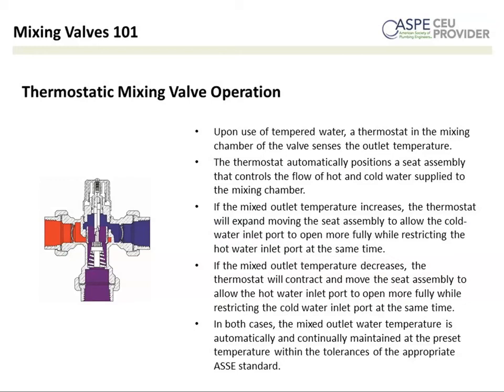And the heart of any thermostatic mixing valve, again, we talked about this earlier, is that thermostat. In this case, it's in the center of that diagram, and it's a paraffin-based element, which has some wax mix, some copper, a diaphragm, and a piston. And based on the temperature of that water, it's moving the piston up and down and essentially increasing the hot while decreasing the cold, or vice versa, to maintain the set temperature.